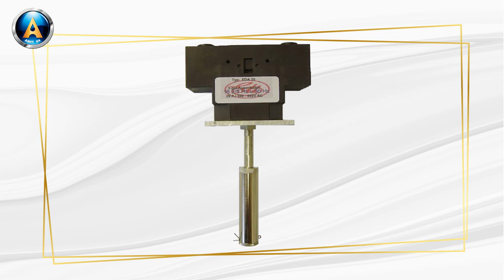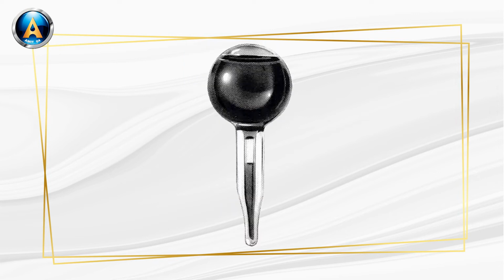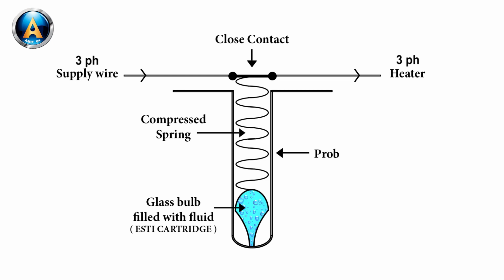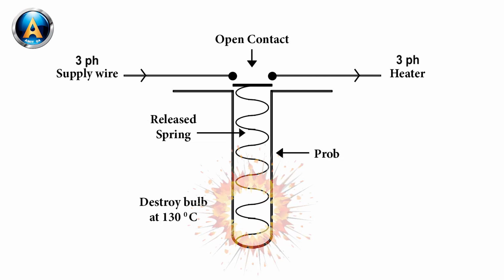The ESTI cartridge inside the probe of the self-destroying type excess temperature protector device is basically a small spherical glass bulb filled with chemically inactive fluid. The internal pressure of the bulb increases at 130 degrees centigrade temperature, for which it destroys. Simultaneously, the spring tension held by the bulb is released and the three-phase supply contact may break.